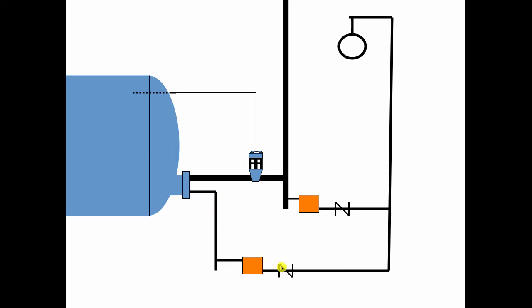And in this case we've got a check valve and over here on the steam supply line we have another trap and another check valve because we decided to give this one an overhead return just to make it more interesting. So the steam's coming down because steam doesn't know up from down, it just knows out, it's looking for an air vent. And we're going to send the steam through a regulator which is sensing the temperature of the water in the tank.